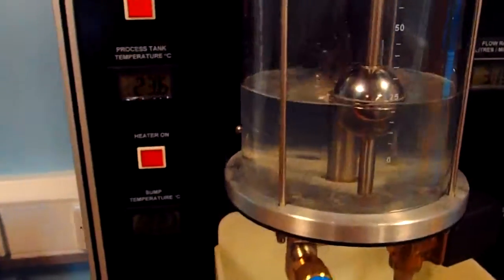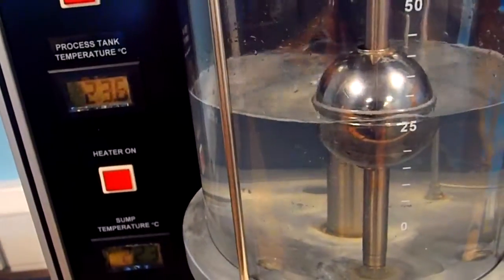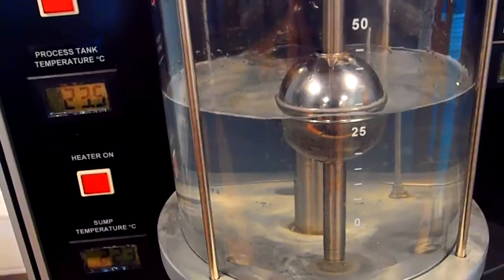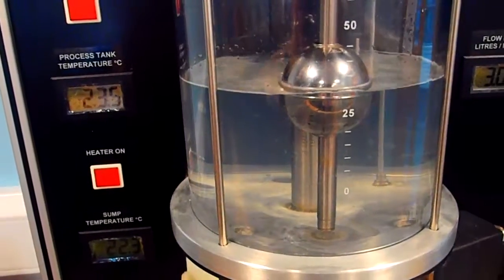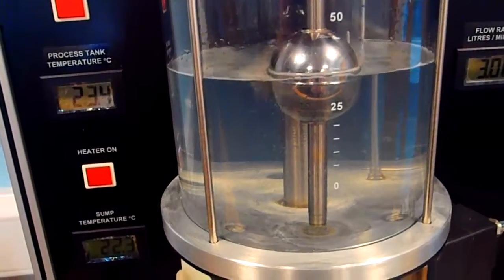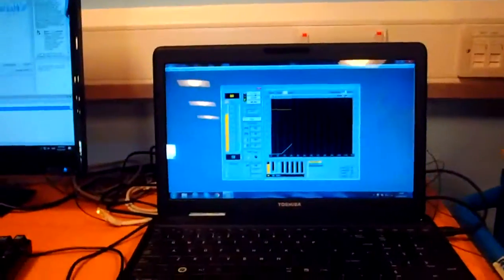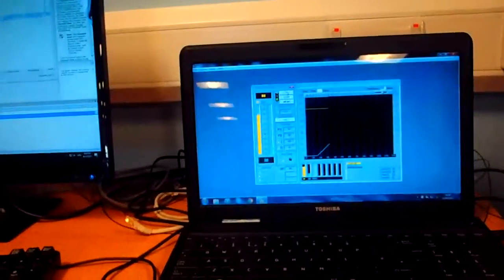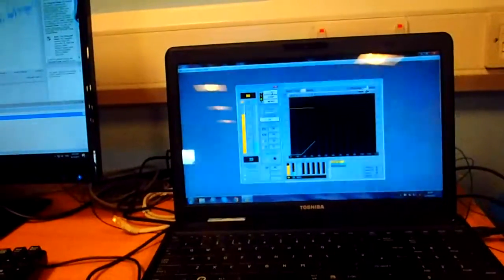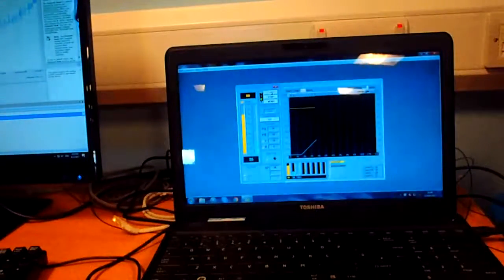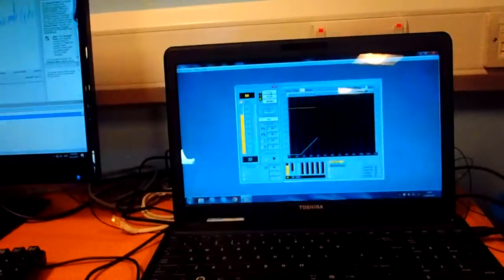It hasn't actually triggered a step change yet, so that would suggest that the calibration of the level sensor is very poor, because it didn't actually start to rise until about 25%. But that won't matter for the purposes of what we're doing, because it was uncalibrated at the time I took the original data.